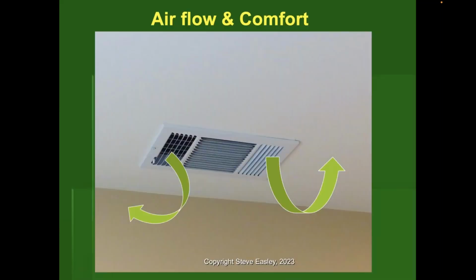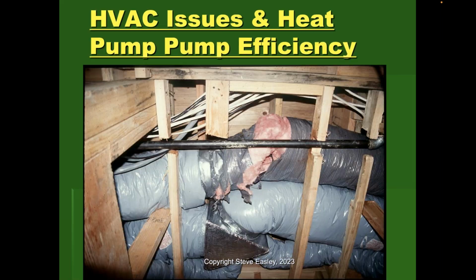And then getting the airflow right, making sure that you have a licensed professional size your system based on whether you're heating or cooling. And this is really important because you want to make sure you get the loads right. You want to make sure you get the ductwork designed right. So typically you use ACCA, the Air Conditioning Contractors Association, Manual J, current version, to calculate the loads or equivalent software. And then use Manual D to design the ducts, Manual S to select the equipment. But spend the money on a professional that can help you design these systems to get the proper airflow you need. And then you have to pay attention to how the ductwork system is installed.